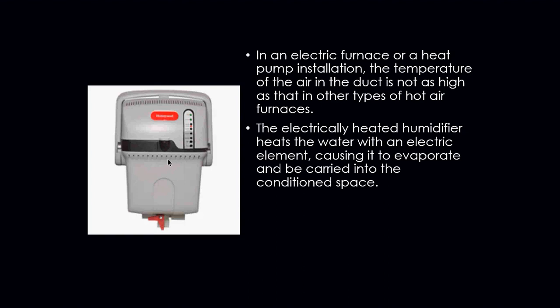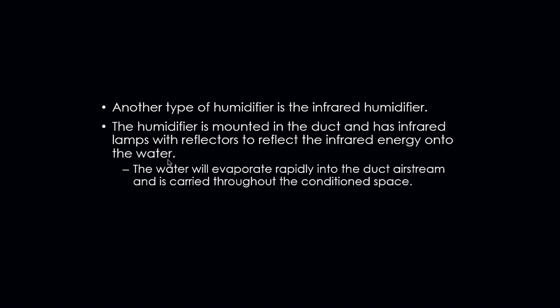So this type of humidifier really doesn't have a pad or some sort of wheel in it. These actually have a heater in there, and as that water is heated up, it now vaporizes into a fine mist. And it is that fine mist that gets carried into the supply ducts or into the ductwork, which will now be carried throughout the space to actually add humidity to the space.